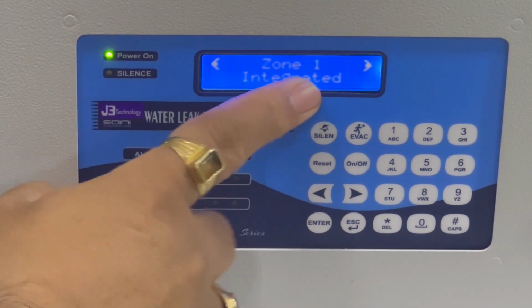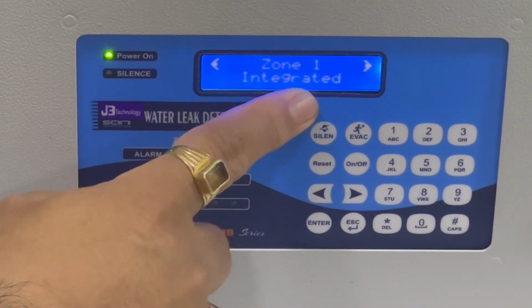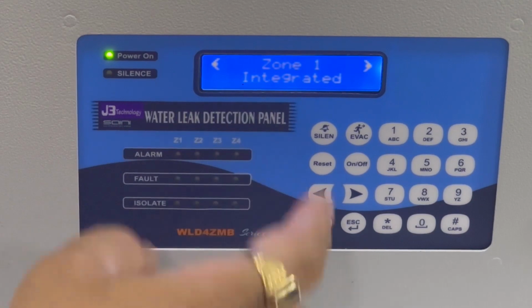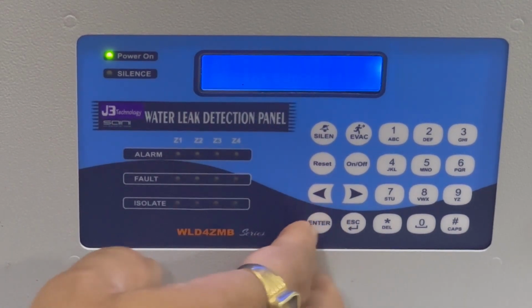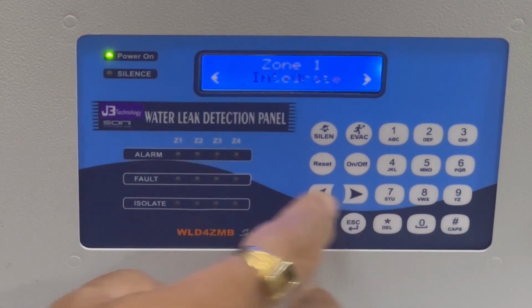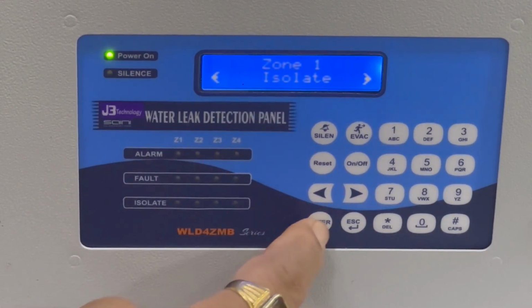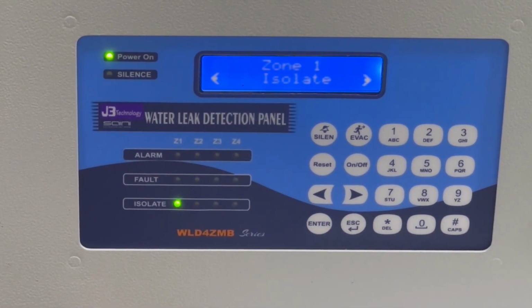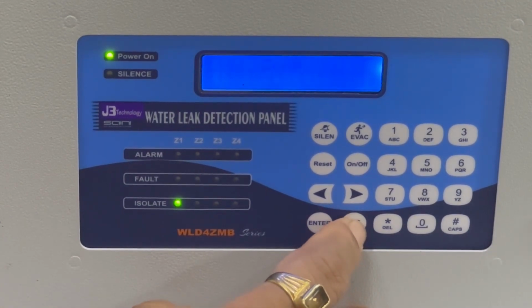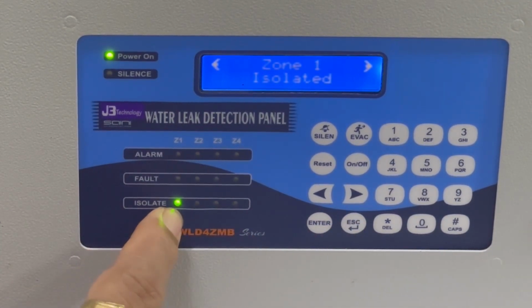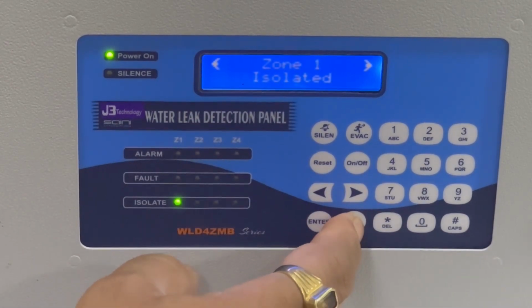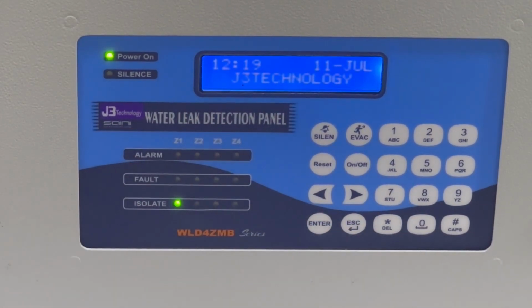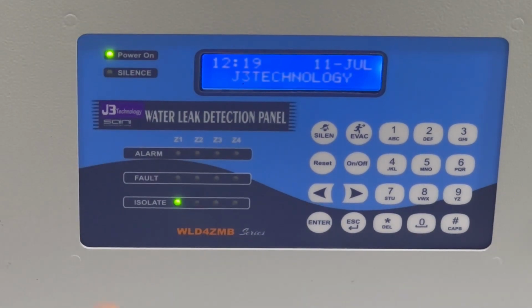Okay, now zone 1 is integrated. Now I want this zone to be isolated, so I just press enter. Okay, just isolate. Now zone 1 is isolated. I press enter to confirm. Now you can see the zone 1 isolated light is on. That means zone 1 is isolated, and no alarm will come whenever water comes and touches the sensor cable.